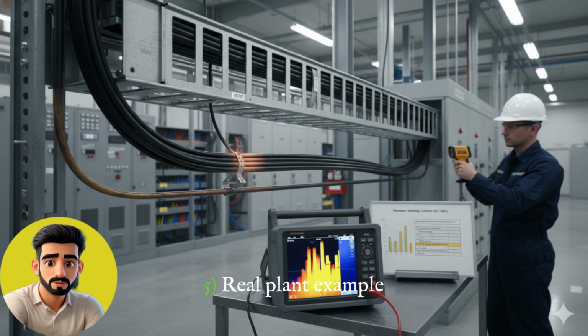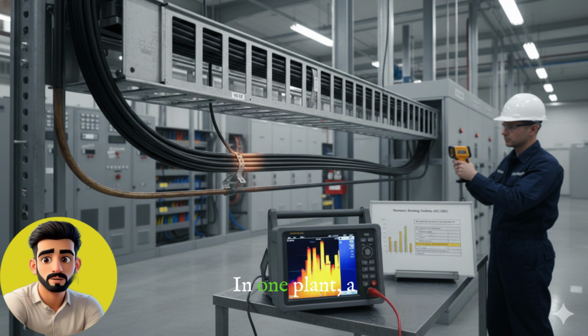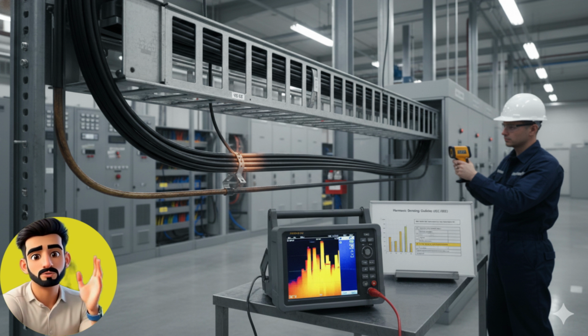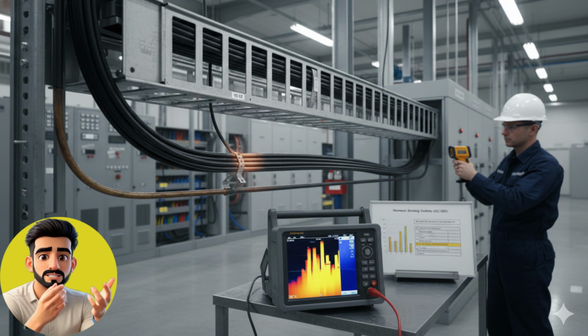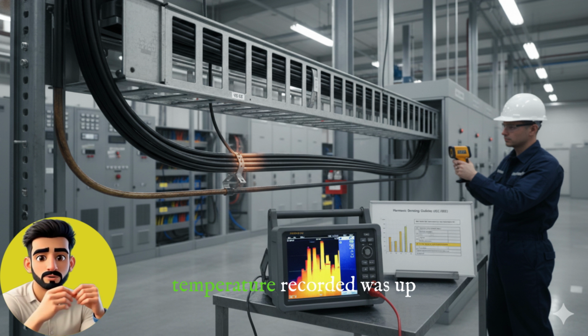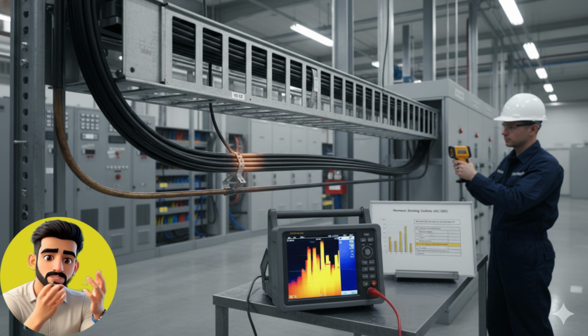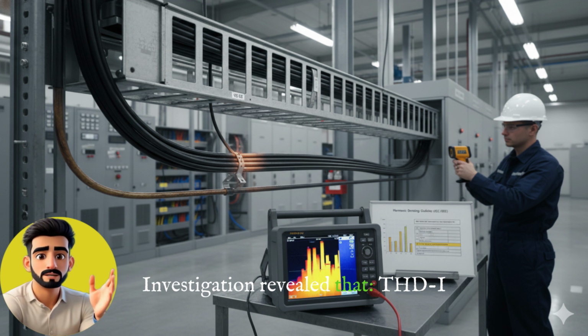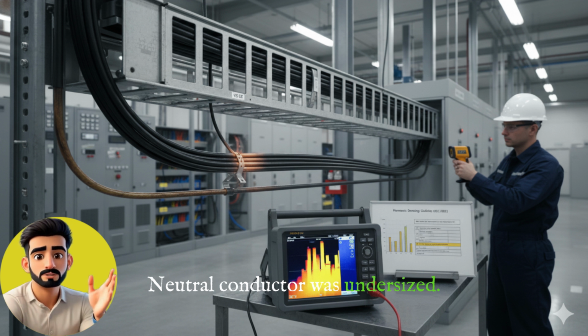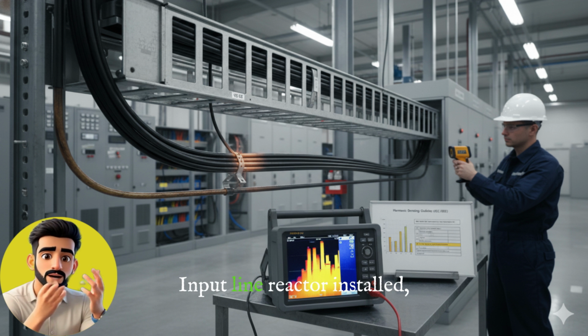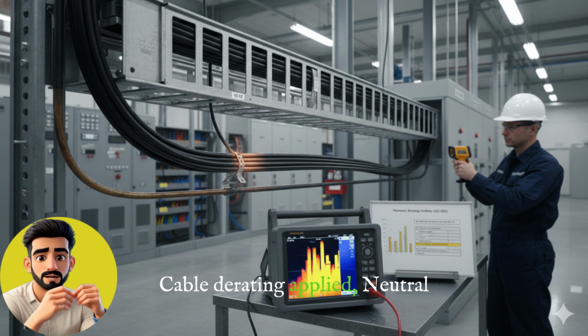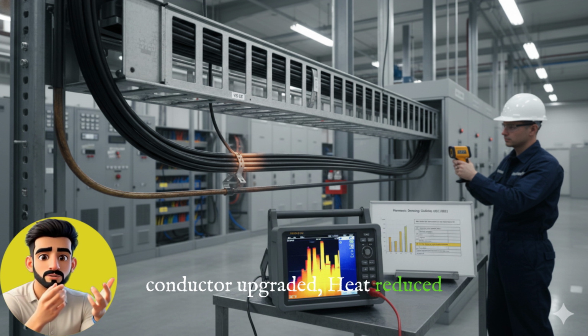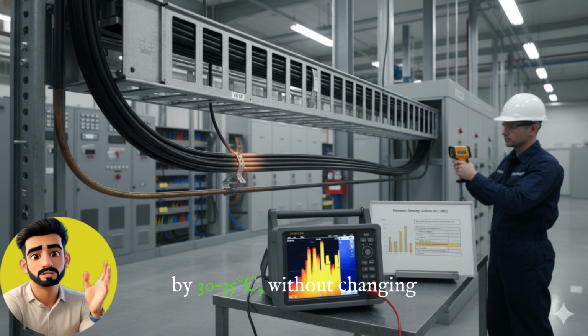5. Real plant example. In one plant, a 75 kilowatt motor was running with a VSD. The load was only 60%, but the cable surface temperature recorded was up to 80 degrees Celsius. Investigation revealed that THDI equals 42%, with 5th and 7th harmonics dominant. Cable derating was not applied. The neutral conductor was undersized. What was the solution? An input line reactor was installed, cable derating applied, and the neutral conductor upgraded.